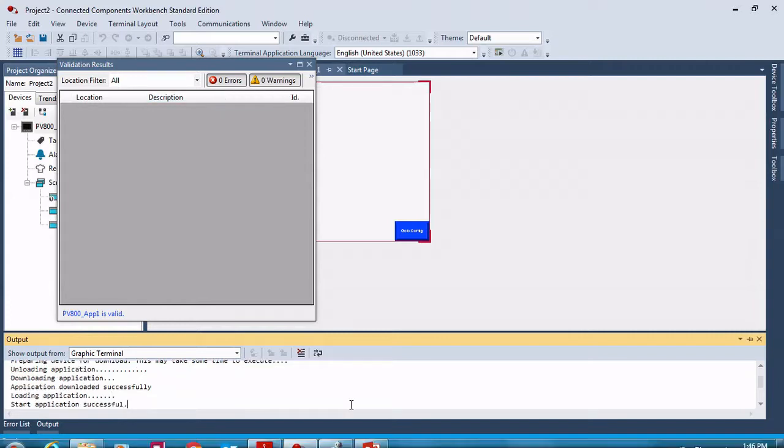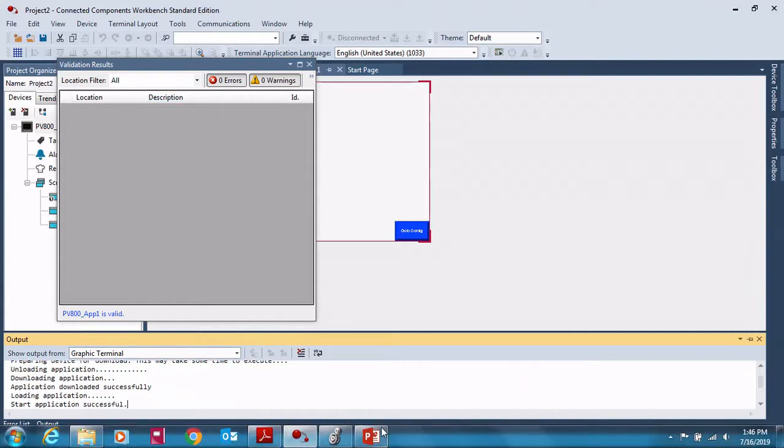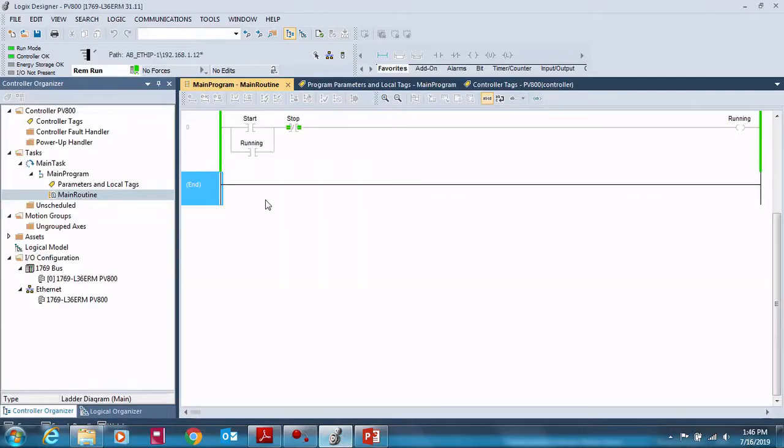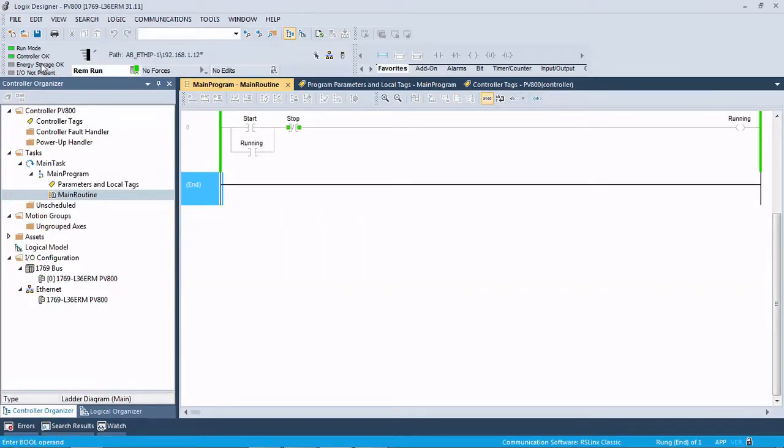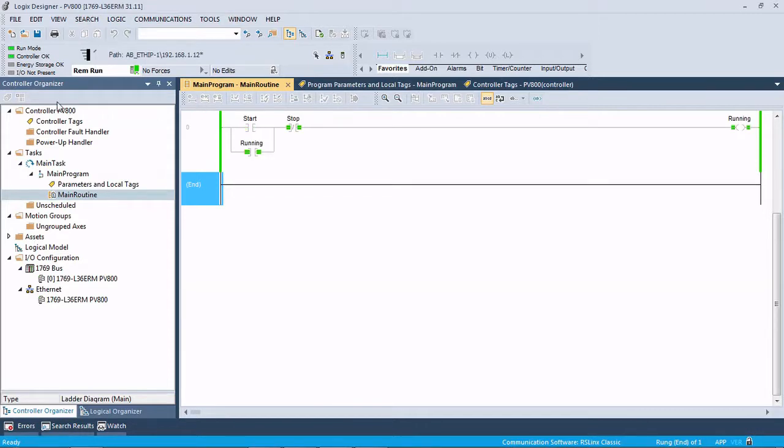Once that loads, it's loaded, it's sitting here next to me. We have this running L36 with our little stop, and here's our start, and our stop from our PanelView 800. So it's pretty straightforward, the only hiccup is make sure you get that comma one comma zero in there, and there you have it.